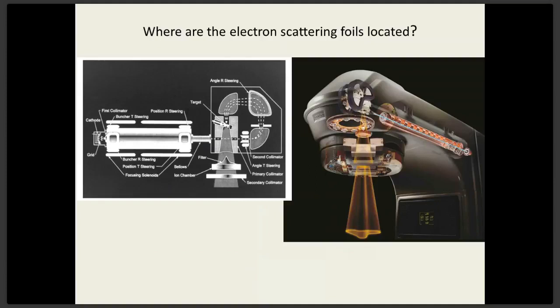This is the anatomy of a linear accelerator. On the left is the beam path, and you see the cathode, which has the filament, the source of electrons, the accelerator guide that accelerates the electrons, and then the electrons enter the bending magnet of the machine, which takes the beam and directs it back down toward the patient. The beam has to pass through a flattening filter. Well, that used to be the case, but now we have FFF, flattening filter-free beams, where the flattening filter is removed, but generally the beam passes through a flattening filter to make it nice and uniform across, and then it passes through the very important ion chamber, which is going to help with the readings and the output.